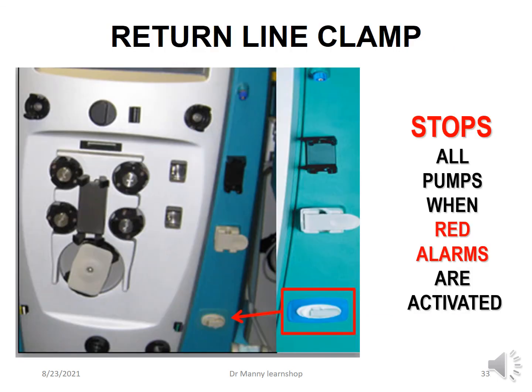The return line clamp is another safety feature that clamps and blocks the line, blocks blood returning to the patient, and it stops all the pumps when red alarms are activated. So if a red alarm is activated, all the pumps stop and the return line clamps down and will not let anything move forward into the patient.